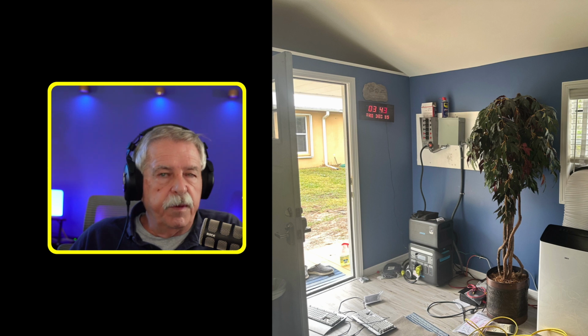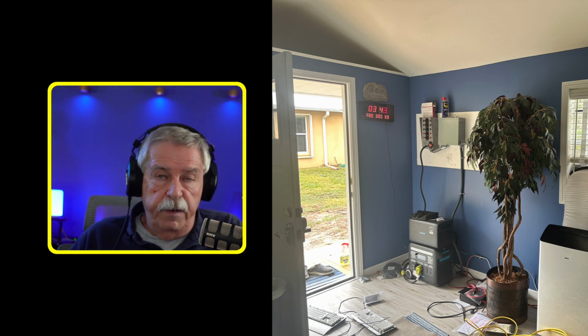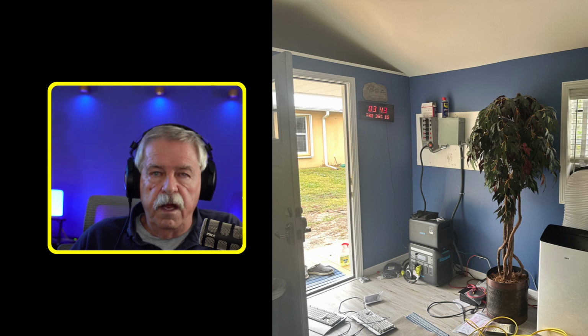Now, was that a real big problem? No. You have to kind of future-proof it as best you can with what you know at the time. So I did not like that I only had 20 amps available. Now, what happens? If you go beyond the amperage, the unit will shut down. So you could be, very much like I am now, in the middle of a presentation, and it could very well just say, whoops, too much power, I'm going to shut you down. And everything goes off, the lights go off, and we're just not having a good time.